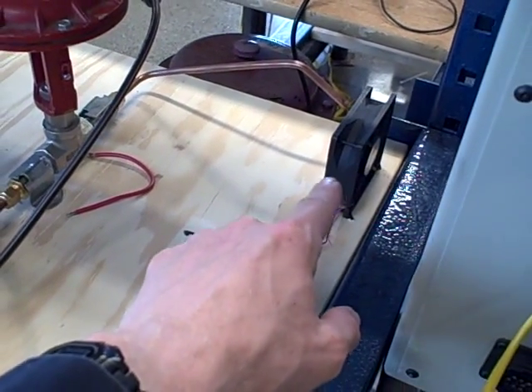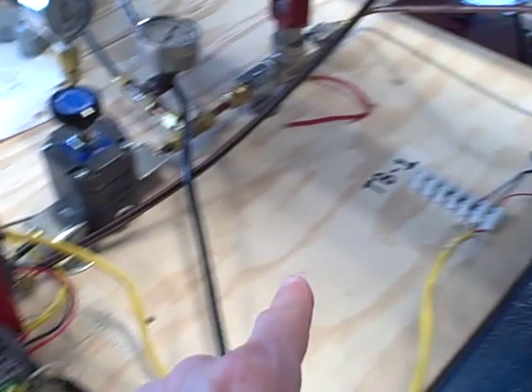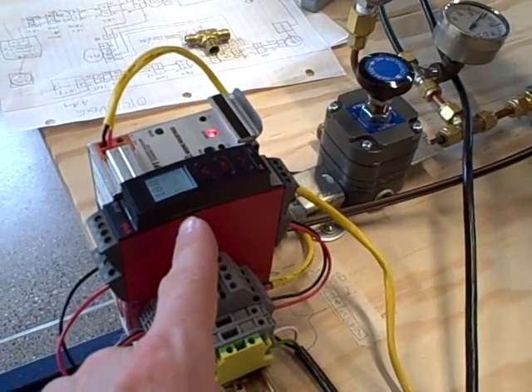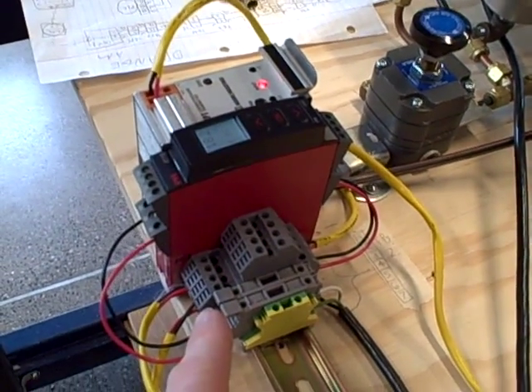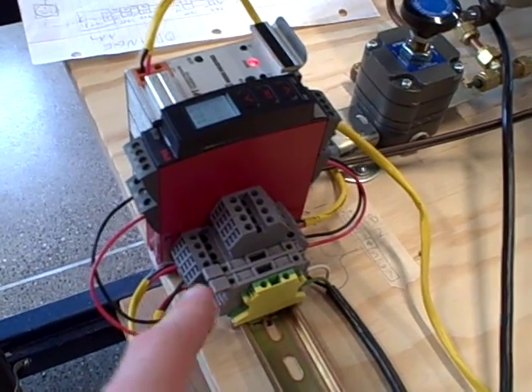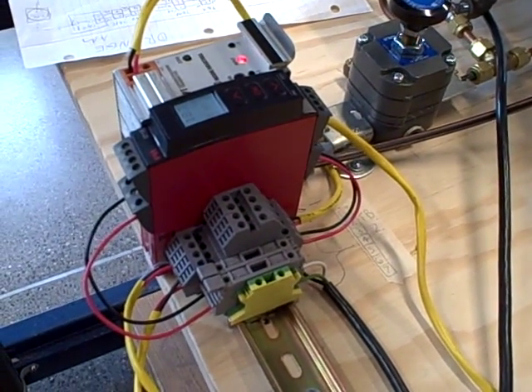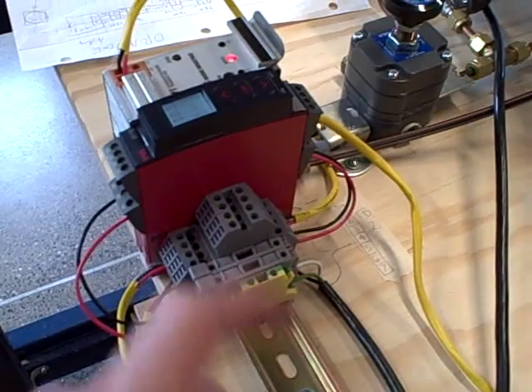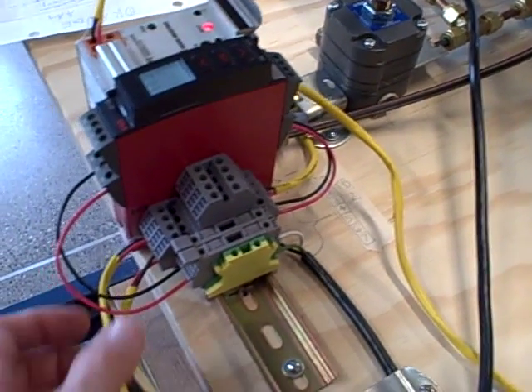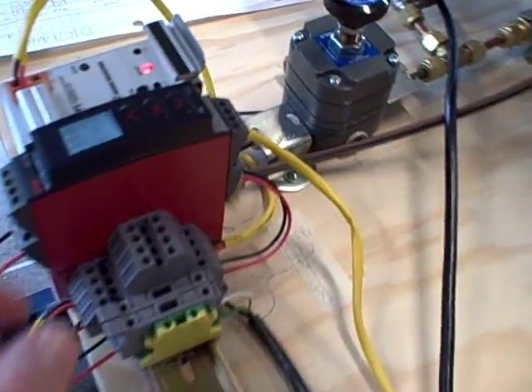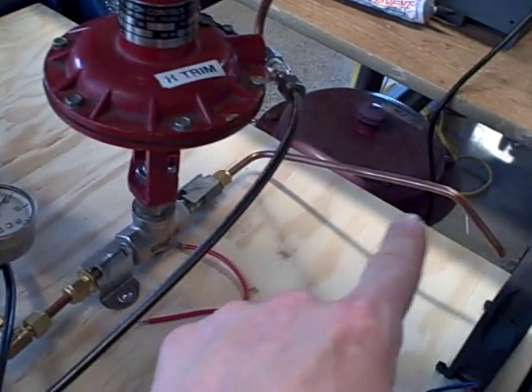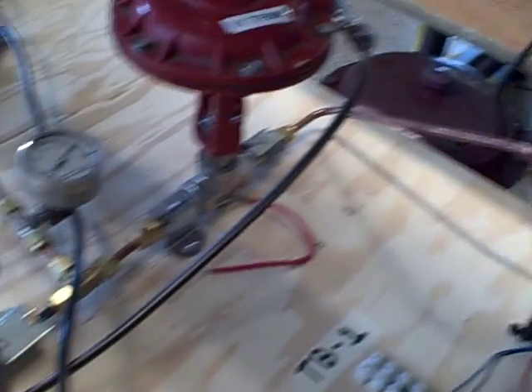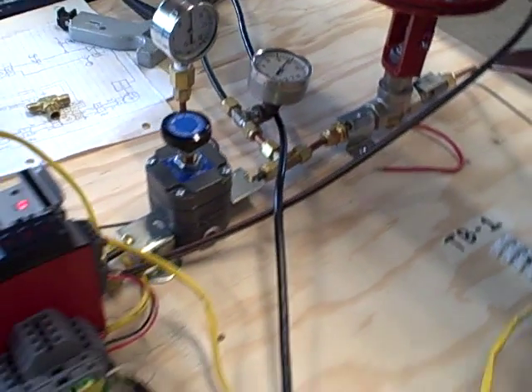It spins the fan blades and generates the DC voltage, which we then convert to a 4 to 20 milliamp signal to send to the PLC as a process variable. The PLC calculates what the output should be, comparing the PV against set point, and it sends an output signal here, 4 to 20 milliamps as well, to go to an I2P to drive the air valve to admit more or less air to the nozzle through the turbine. So we have a speed control system for the turbine.